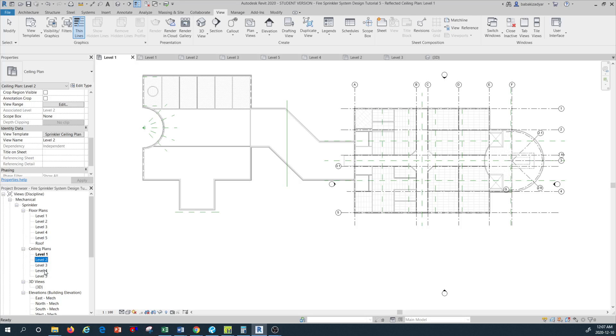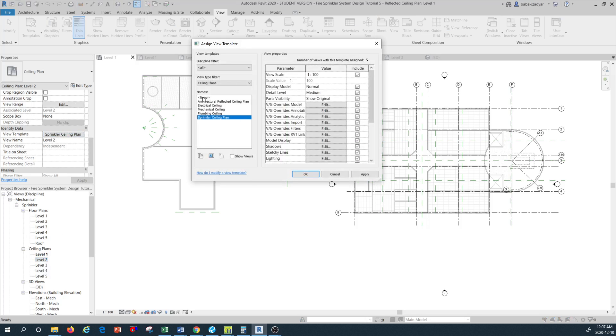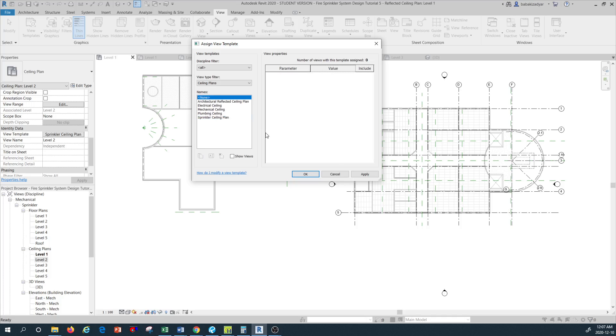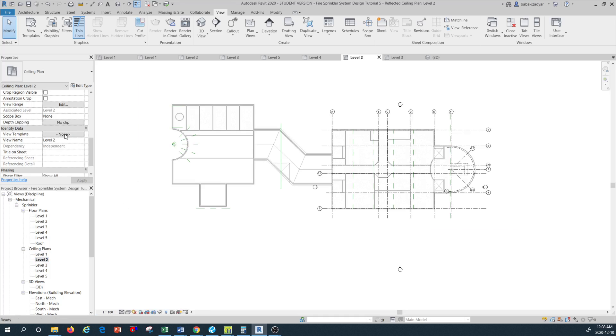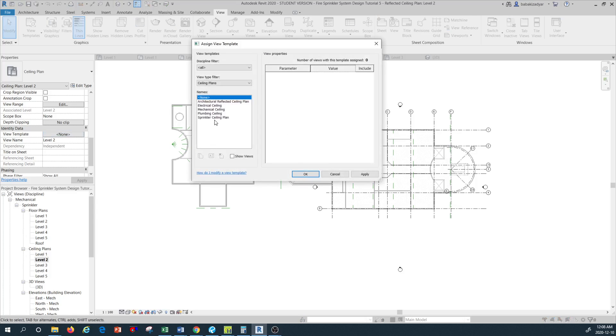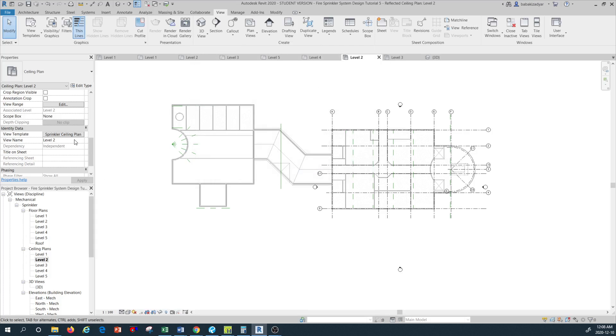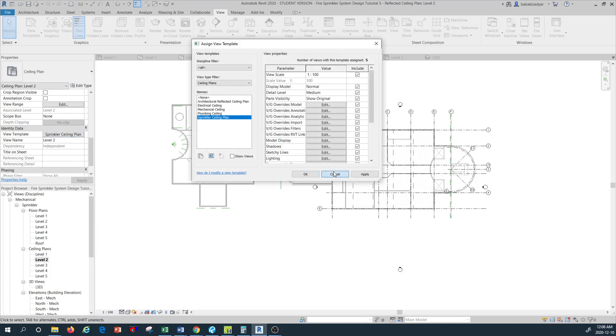If you don't want to show anything in a specific template, at any time you can set the view template to None and make changes that aren't visible in any template. When you're on None, you also have the option to change the scale — this is not possible when you have a view template like Sprinkler Ceiling Plan assigned. With a template applied you can't change the scale; you have to set the view template to None first to make that change.